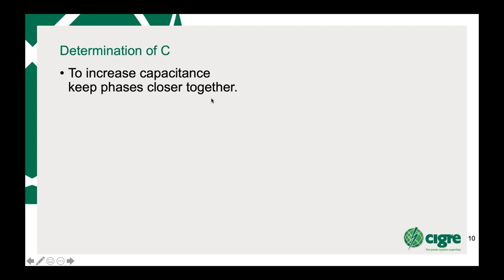So what we have with resistance, you can use larger conductors, you can use more aluminium per phase. That's either in bundle configuration or large conductors. And then for L, you just keep the phases together. And for C, you keep the phases together. So it looks quite simple. Have a compact line with large conductors and you won't have a problem.